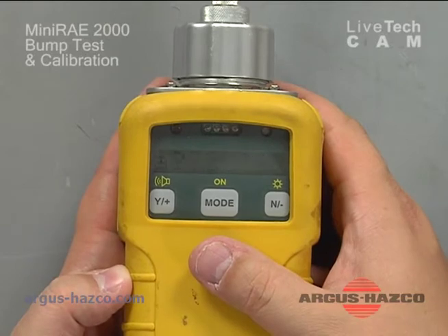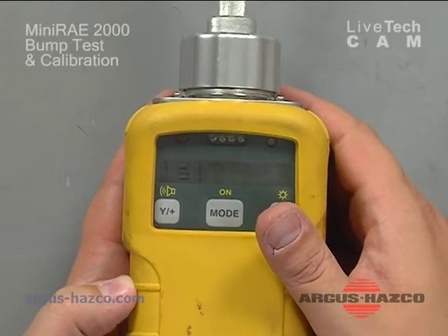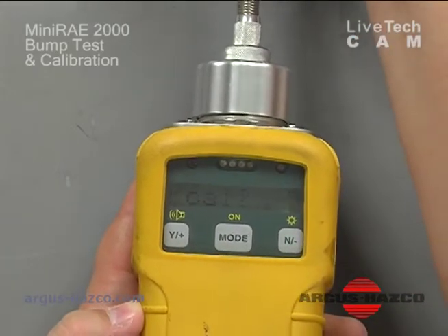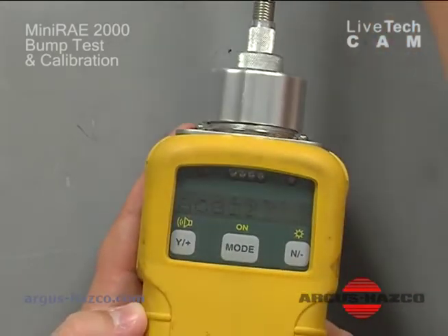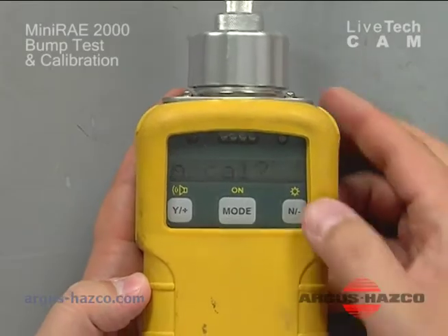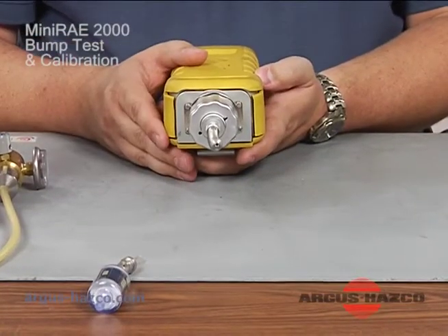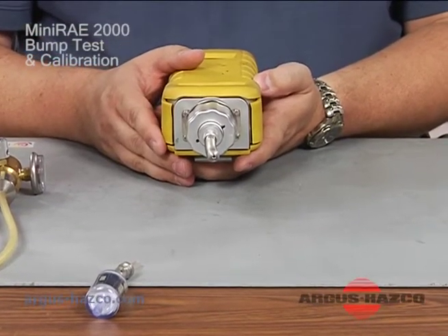You hit your mode button, and it's going to ask, do you want to span cal? At this point is when you can calibrate the monitor. But we're going to bypass that and do a bump test at this point. So, no, we do not want to span cal. Then it's going to say, do you want to select a cal memory?